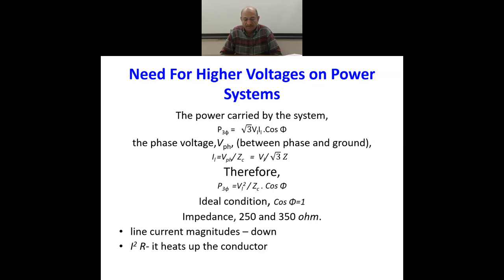We also know that V_phase — the phase voltage — is the line voltage divided by √3, meaning the voltage between the phase and the neutral. The line current would be V_phase divided by the impedance. Here we have taken Zc, which is the characteristic impedance of the transmission line. The line current works out to be V_line divided by √3 × Zc. Therefore, the three-phase power works out to be V_line² / Zc × cosφ. Under ideal conditions, we can assume cosφ = 1.